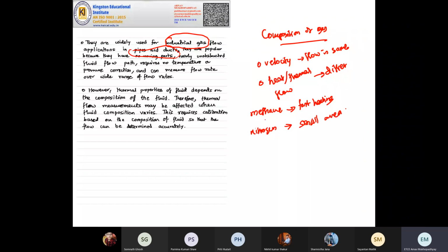Like that, you can detect the presence of different gas components by detecting how much is the flow rate using this meter. So you need to calibrate it properly. Calibration is essential for this meter. If you calibrate it wrongly, for instance, you calibrate this instrument to detect methane and you are trying to measure the flow rate of nitrogen, you will get an error. So you have to calibrate it properly.